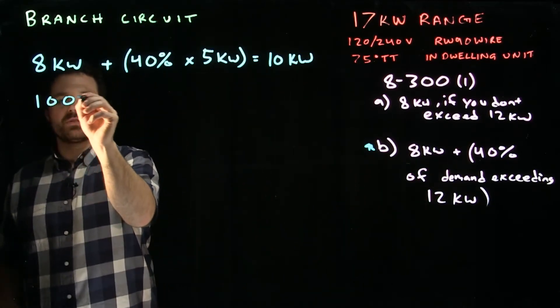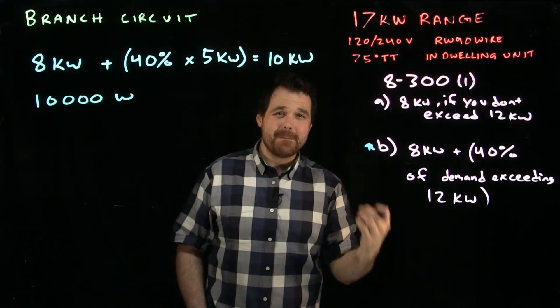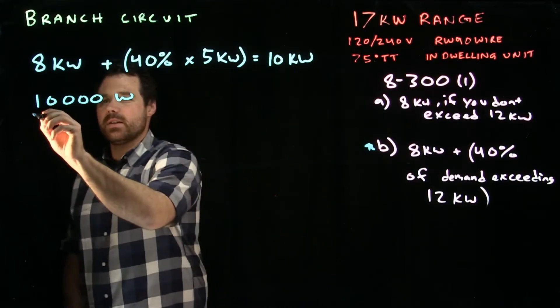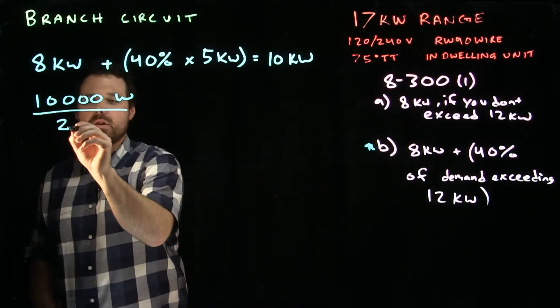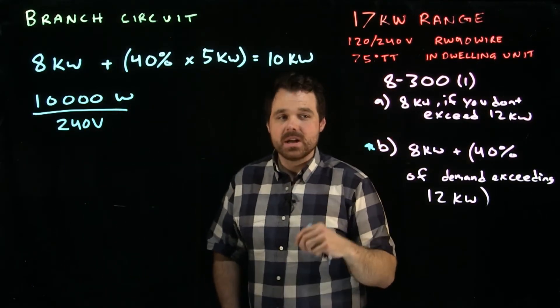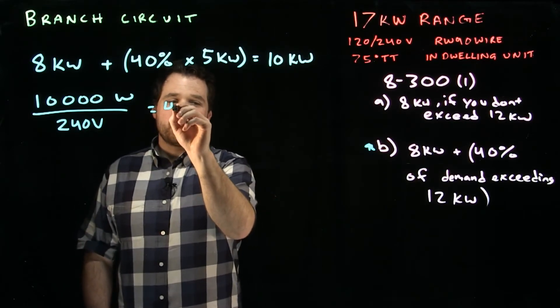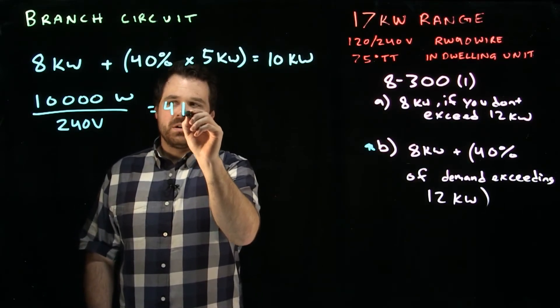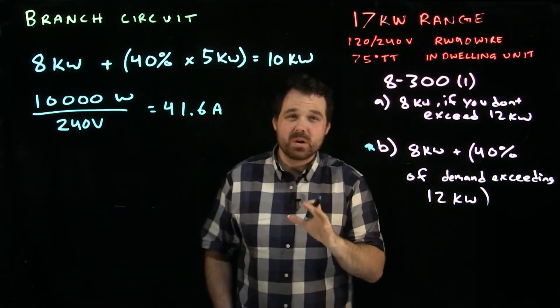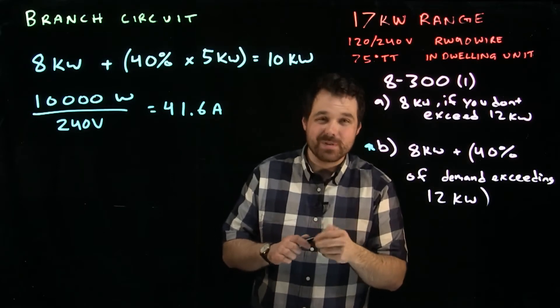So take our 10,000 watts, our 10 kilowatts. We need to now turn that into a minimum ampacity or a required ampacity of our conductor. We divide that 10,000 by 240 volts. We want to use the line to line voltage of our range. So we divide by 240. This gives us 41.6 amps. So 41.6 amps is the minimum ampacity of our range conductor.